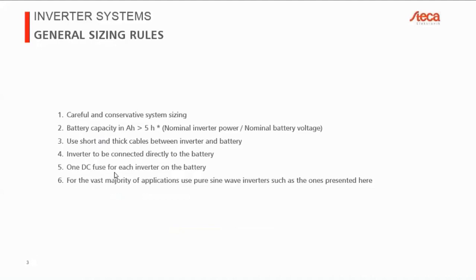And the second reason is that if you make the mistake of connecting the charge controller and the inverters on the same fuse, and that fuse blows, then what happens is the charge controller will not have a battery to regulate the voltage. So at least for a very short amount of time, usually the charge controller protects from this, but there can still be a small peak. The PV voltage will basically be visible on the battery connectors. And if the inverters are directly connected to those battery connectors via the same fuse connection, then the inverters could be damaged by the high PV voltage. So if we put a fuse separately on each charge controller and separately on each inverter, we don't have that issue. So this is our strong recommendation.